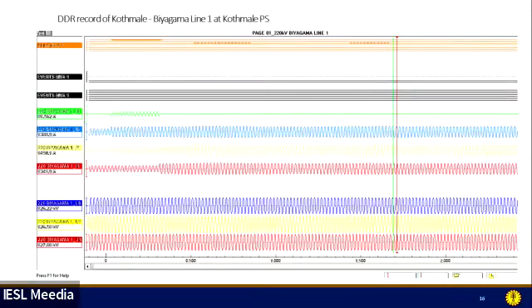This is a snapshot of the digital disturbance record obtained from the Kothmale end of line 1. So in this line, what happened was the backup earth fault protection relay operated. The backup earth fault protection initially got a high startup current because of the auto-reclosing process that happened in the parallel line. At that time the neutral current was about 400 amperes. After that, there is a persistent high neutral current because of some unbalance in the transmission network, around 65 amperes throughout this process. Because of that high unbalanced current, the relay operated after about 10 to 12 seconds.